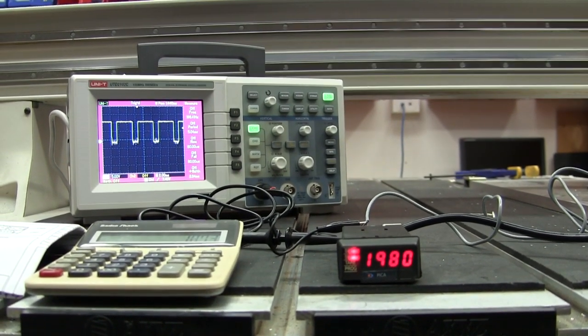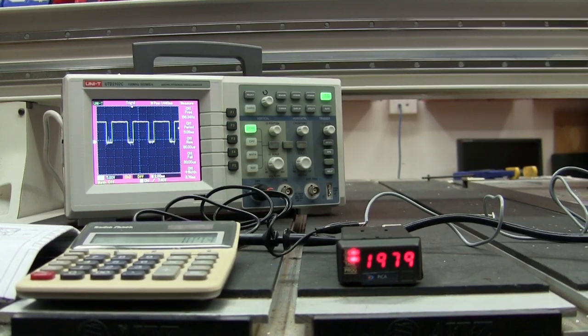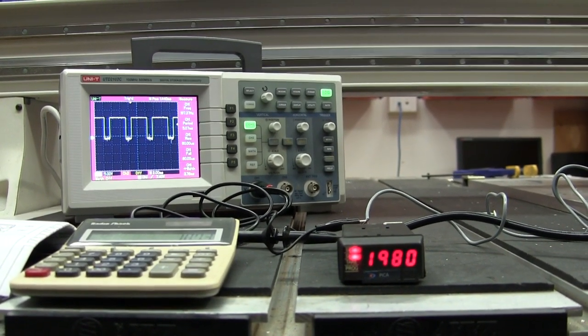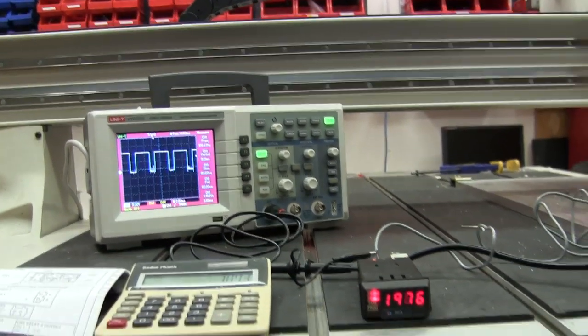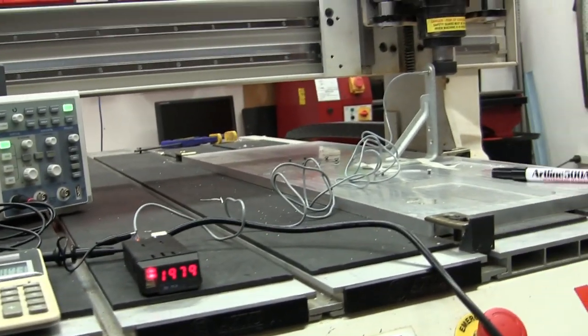So, I'll just adjust this so it's a little bit more stable here. OK, that's where it should be. So, it's sort of floating between 10 RPMs. So, it's within 1% or so of what's really going on. So, alright, so this is how we've set up the RPM meter with an inductive sensor. And I think that's probably the better way for you to go. If you have any questions, please give us a call. Thank you.